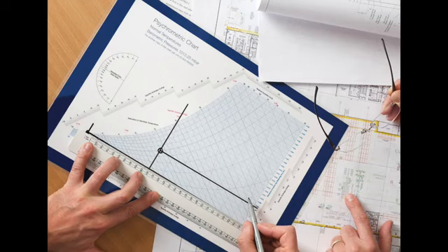So by plotting our building's starting air condition and our required end condition on a psychrometric chart, we can calculate how much moisture we need to add to 1 kilo of dry air to get it from starting point A to its end point B. And once we know this, we just need to multiply this amount of water by the overall air volume flowing through a room or a duct. And then we have our humidifier size.